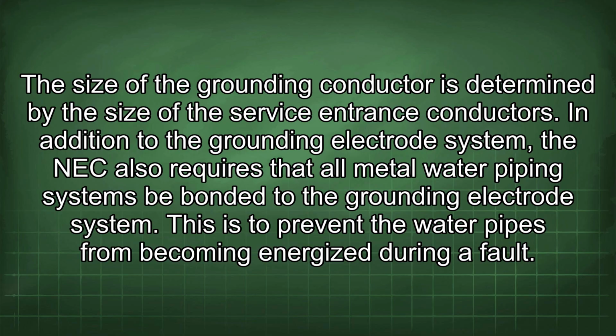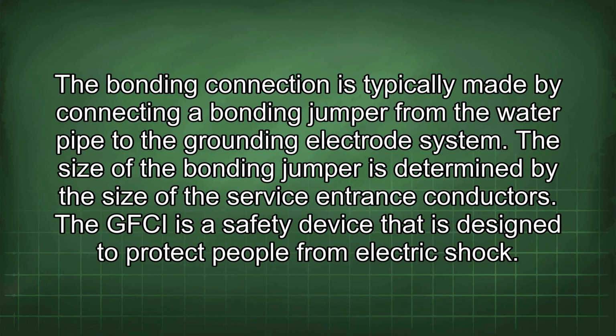In addition to the grounding electrode system, the NEC also requires that all metal water piping systems be bonded to the grounding electrode system. This is to prevent the water pipes from becoming energized during a fault. The bonding connection is typically made by connecting a bonding jumper from the water pipe to the grounding electrode system. The size of the bonding jumper is determined by the size of the service entrance conductors.